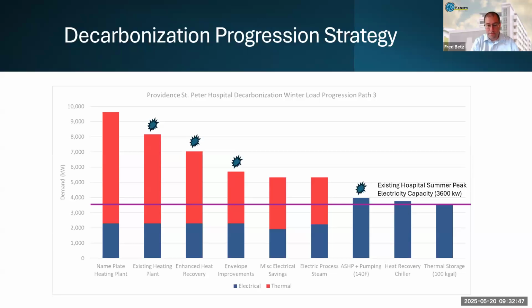So we finish that implementation, save about 300 kW across the facility, but we use up that 300 kW by electrifying their process steam loads, which the two big ones in this case are central sterile and the steam dishwasher in the kitchen. There's other steam loads as well, but those are the two big line items. And again, I'm going to harp on data here. If you have 5 sterilizers that need 200 pounds per hour of steam, the peak load is not 1,000. It's not even close. It's closer to 200 than it is 1,000. And the reason is they don't all run at the same time. It's not a flat out steam demand that cycles through. And so getting sub-meter data for your sterile processing of how much steam you actually need is a huge demand savings. I can't emphasize the data enough.